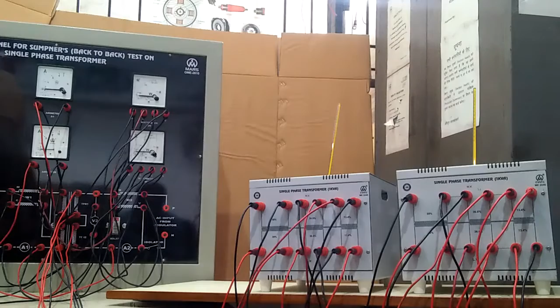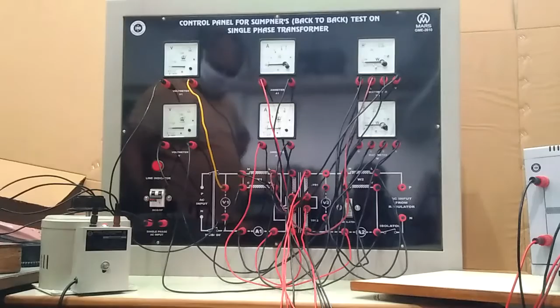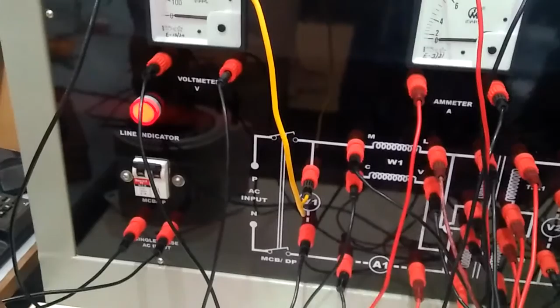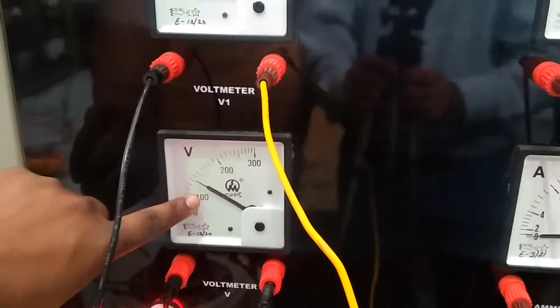Now fix the thermometer. The place is given above the transformer as shown here. Now for the additive or subtractive polarity, we will check with the help of the variac. For checking this polarity, we will supply the panel through the AC variac. Now connect the AC supply through the variac and we will check the meters. The variac should be at minimum position. Give the voltage slowly. The above voltmeter shows the input and the below meter shows the output of the transformer.